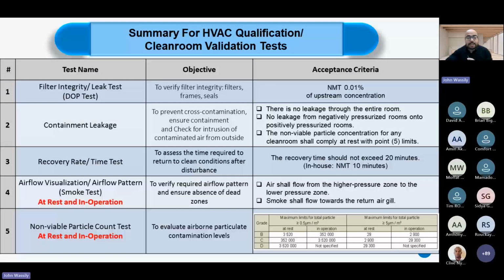Also important is to perform an airflow visualization or smoke test. This is to visualize the airflow and to make sure that the air is flowing from the highly pressurized rooms, which are usually the rooms having the highest cleanliness grade, like grade B, for example, to the lower pressurized rooms, which are rooms of less cleanliness grade, like grade C.